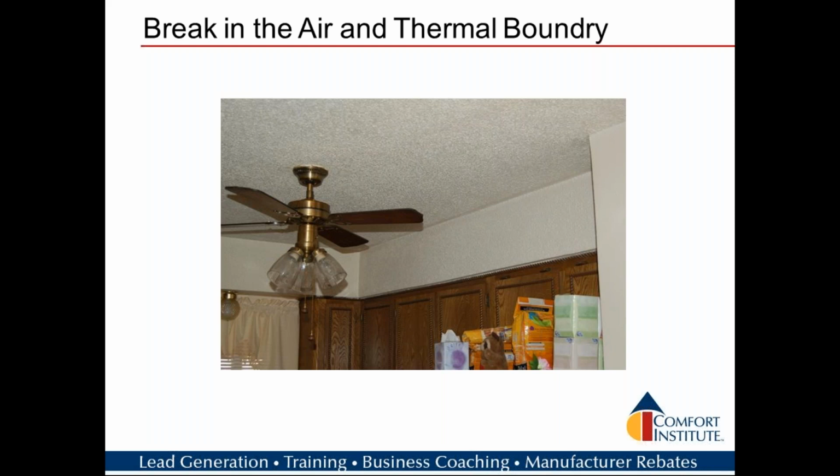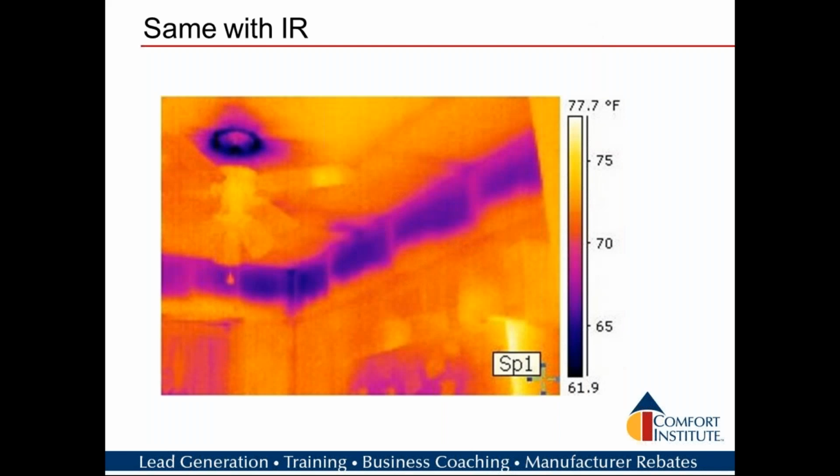Well, if you've got the ability to do a quick little load on the home, you find out what they've got for airflow. And if it is enough coming in, maybe there's something else that's happening. In this particular situation, we had a fur down that was open to the attic space above. Again, not a hard fix. You put a top on it, you put insulation back over it, and you bring that space back into the house rather than being into the attic. Something you can do? Sure.